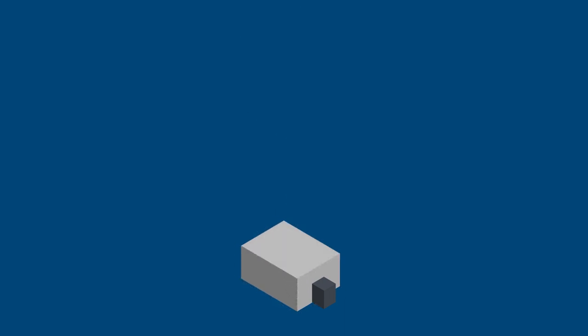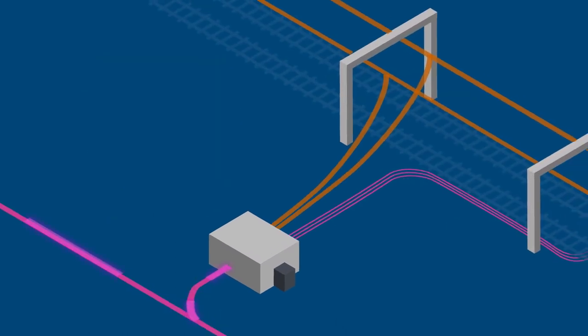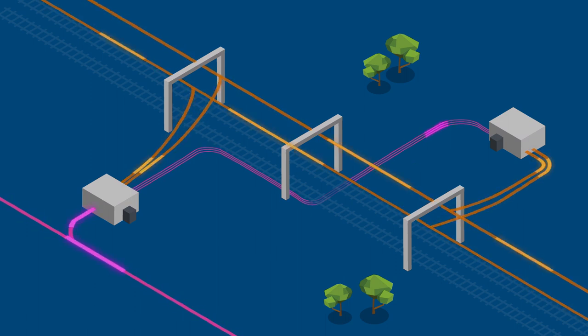There are lots of different configurations of substations around the network. Some substations have outdoor switchyards, some have indoor enclosed high voltage equipment. Substations may look physically different; however all substations perform the same function: convert AC power to DC power for the trains and provide fault protection for the 1,500 volt DC overhead wiring.